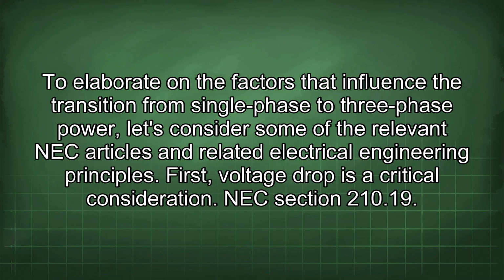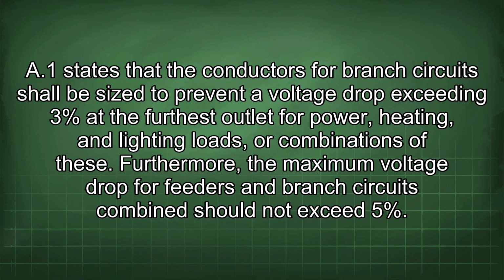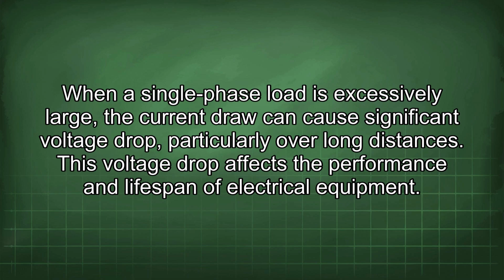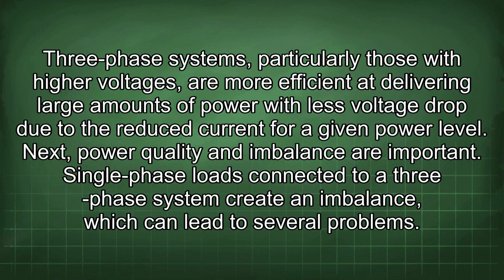First, voltage drop is a critical consideration. NEC section 210.19(A)(1) states that the conductors for branch circuits shall be sized to prevent a voltage drop exceeding 3% at the furthest outlet for power, heating, and lighting loads, or combinations of these. Furthermore, the maximum voltage drop for feeders and branch circuits combined should not exceed 5%. When a single-phase load is excessively large, the current draw can cause significant voltage drop, particularly over long distances. This voltage drop affects the performance and lifespan of electrical equipment. Three-phase systems, particularly those with higher voltages, are more efficient at delivering large amounts of power with less voltage drop due to the reduced current for a given power level.